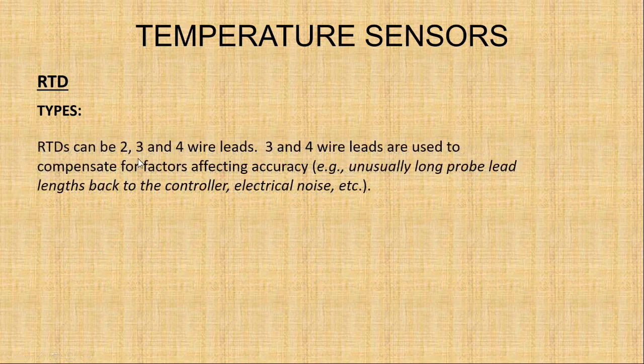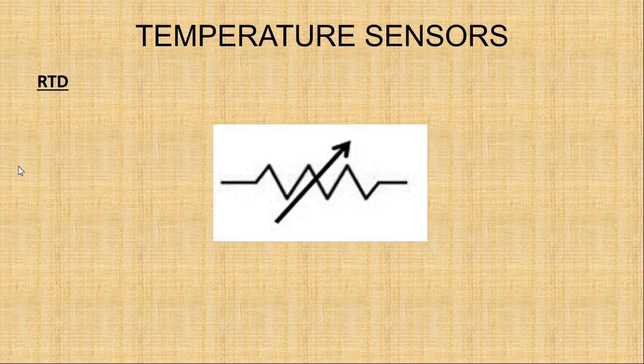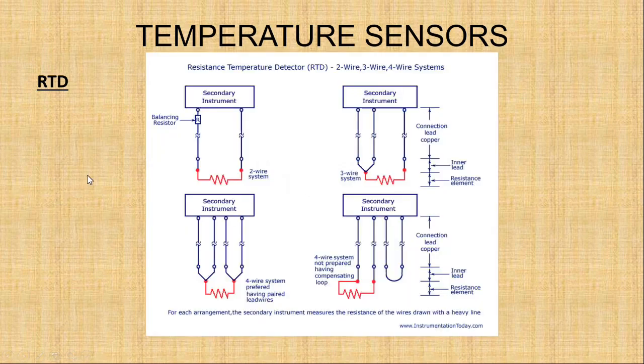RTDs can be 2, 3, or 4 wire leads. 3 and 4 wire leads are used to compensate for factors affecting accuracy. Examples being unusually long probe lead lengths back to the controller, possible electrical noise, and so on. Here's an electrical symbol for an RTD. It looks like a resistor with an arrow through it. Here is a diagram showing the 2, 3, and 4 wire configurations. We won't get too much into that, but basically the probe will come with 2, 3, or 4 wires, and the secondary instrument will only be set up so it can use that particular type of probe.